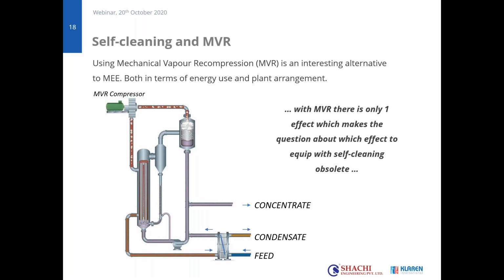But how do you get this system to work? Well, that is done by using a compressor. So by a compressor, you upgrade the vapor. You want temperature, because with temperature, you can create the driving force to run the heat exchanger in the system. But you create this temperature by increasing the pressure. So the compressor increases the pressure and then implicitly also increases the temperature, which gives the driving force. I'll just take my spotlight again, which creates the driving force to run this heat exchanger.